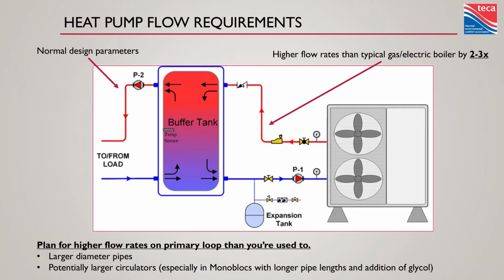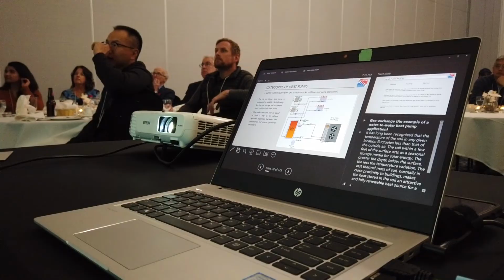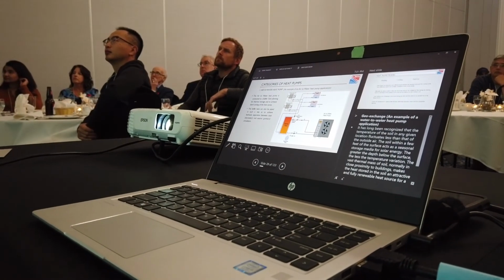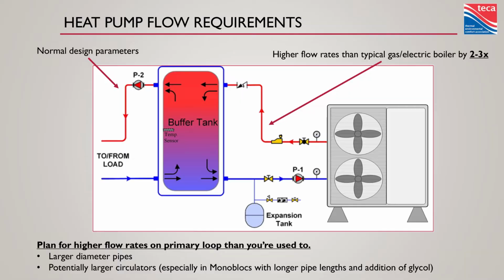Buffer tanks have very little pressure drop because it's a very low velocity through them. Great big chamber, low flow rate comparatively. So that acts like a low loss header. On this side we have our primary circuit where our heat source is just interacting with the buffer tank, and on the load side we've got our secondary circuit drawing heat away from the buffer tank. As far as we're concerned, after that buffer tank, everything is back to normal. Keep it low temperature, but you don't have to change how you're dealing with flow rates and things. It's just on the primary loop that you need to deal with these higher flow rates. So normal design parameters, higher flow rates than your typical boilers.